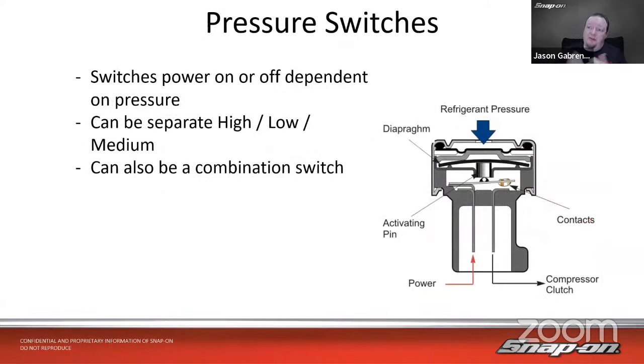Then we have pressure switches as well. So they can be on or off dependent on pressure. And we can also have separate high, low, and medium switches, and it can also be a combination switch, which has high and low in it as well. So the refrigerant pressure is going to push down on a little diaphragm, which will activate the contact, close the contacts. So in this case, we have power going up, and then when the pressure gets high enough, it's going to close on this, and then it goes out to the compressor clutch. In this instance, always check your wiring diagram. But in this particular instance, that's what grounds the clutch or provides power to the clutch. And then that allows it to turn on. So it just kind of depends on whether it's high, low, or other.